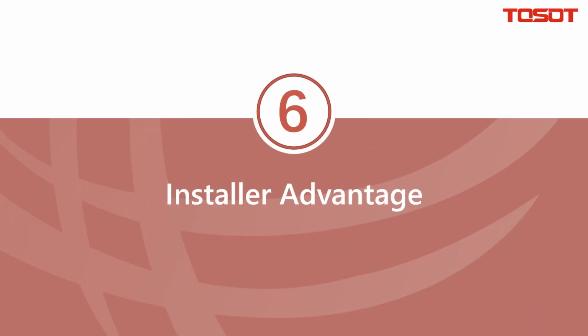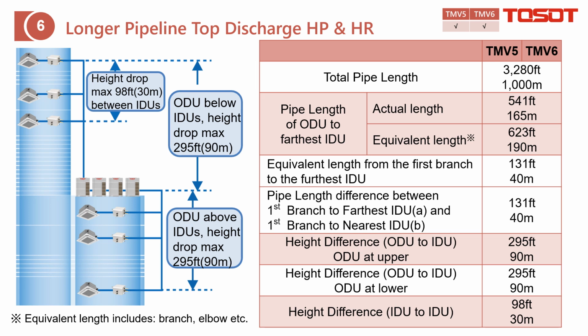Installer advantage. This slide is the comparison between the GMV5 and GMV6 systems. You can find that GMV6 shares the same values as GMV5. The total piping length is about 3,300 feet. From the outdoor unit to the farthest indoor unit, it is around 540 feet. And for the height difference between outdoor unit and indoor unit, whether the outdoor unit is higher or lower, it is around 300 feet, which is about 20 floors. We consider this value quite enough for most projects, so we don't extend it.